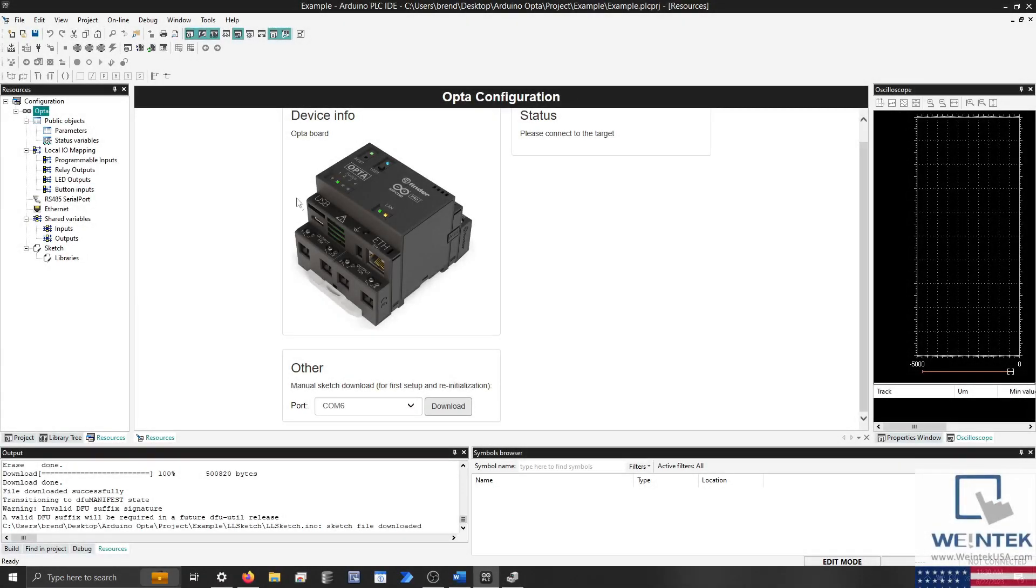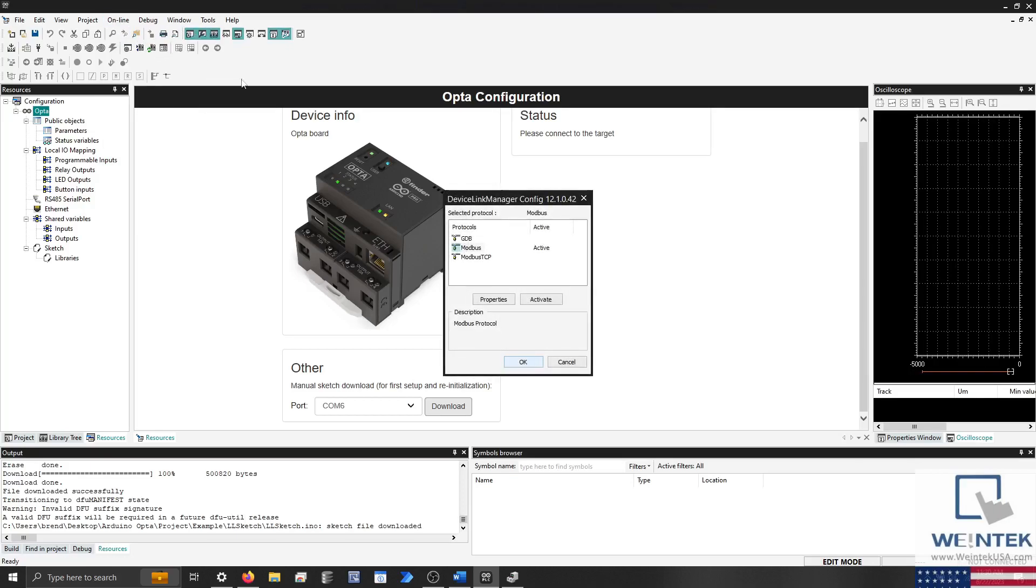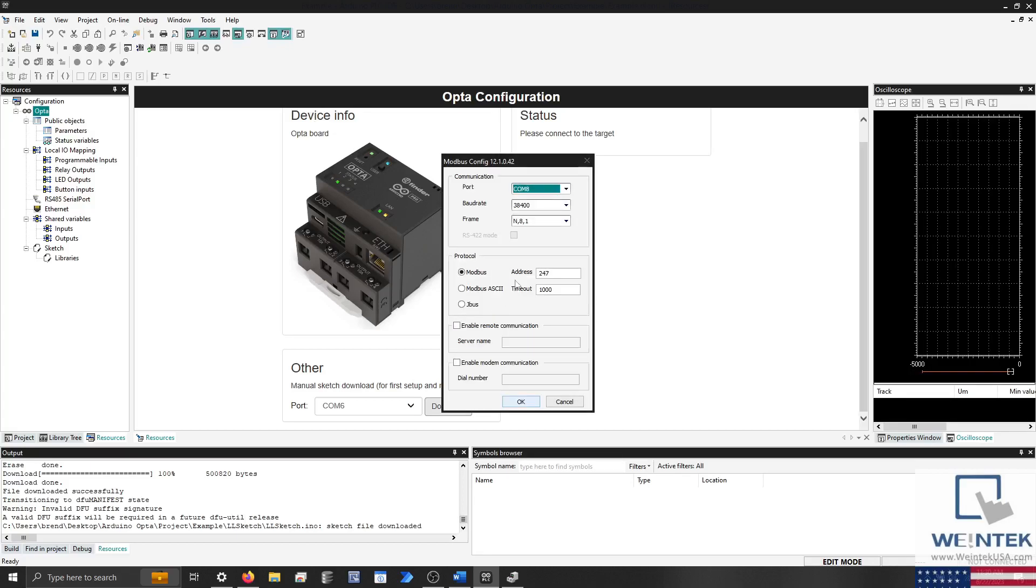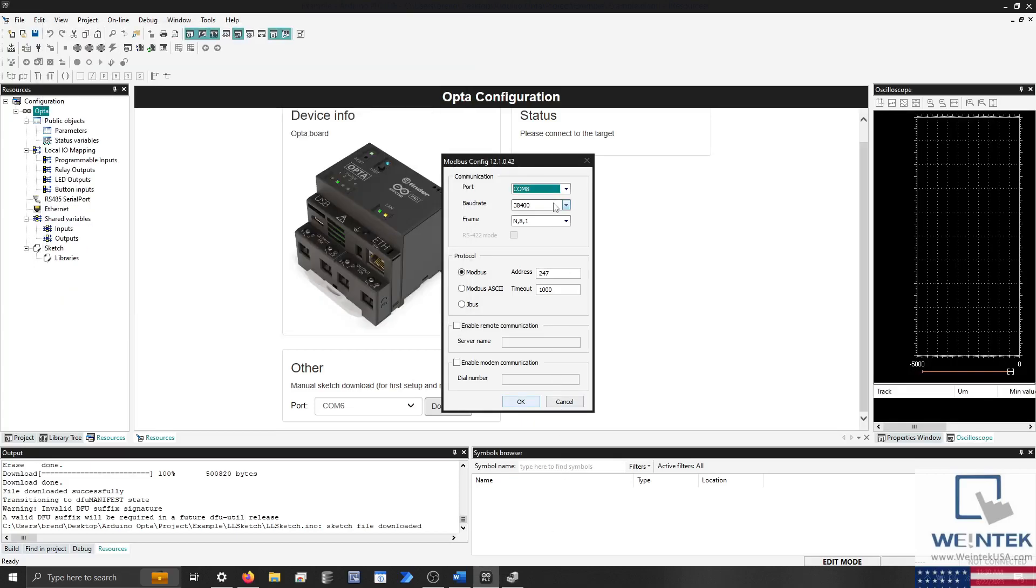When finished, click on Set up communication within the Online tab. With Modbus selected, click Properties, ensure that the virtual port used for Modbus is selected, and that the address is set to 247. This address and all other communication settings may change if you activate a different protocol.